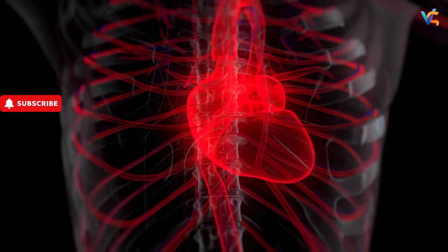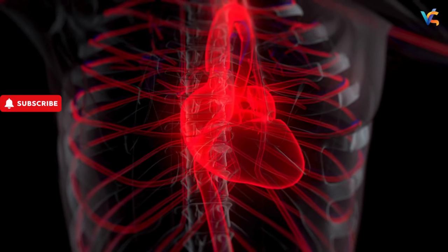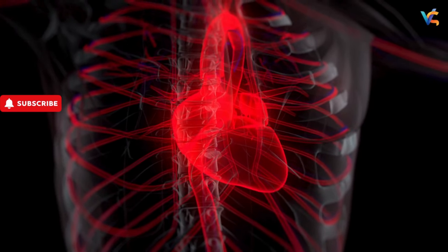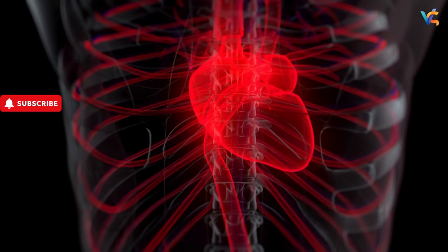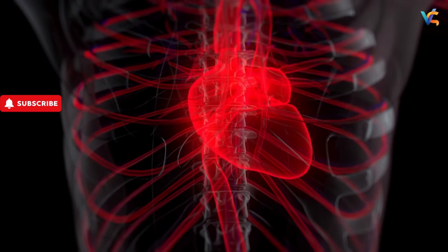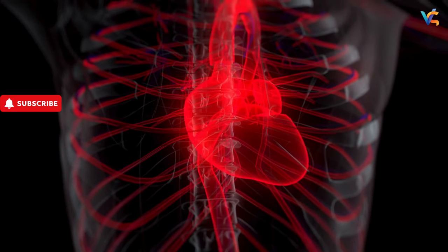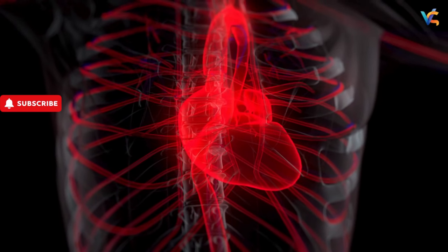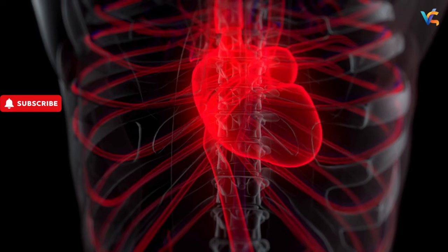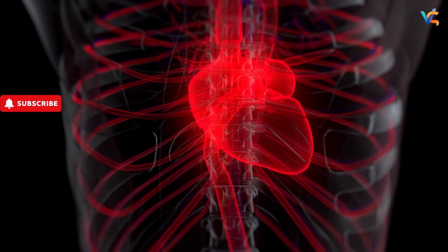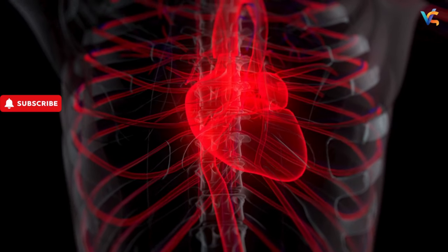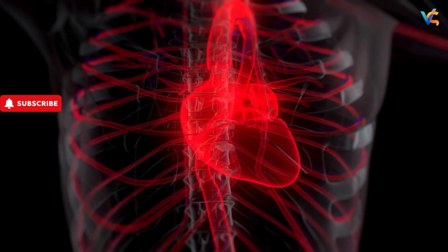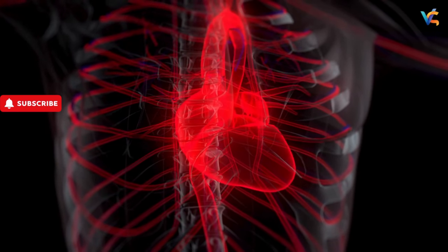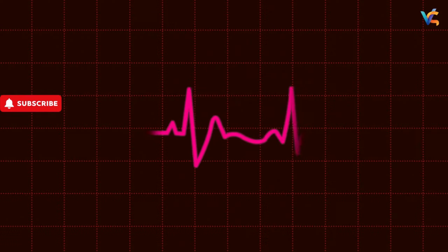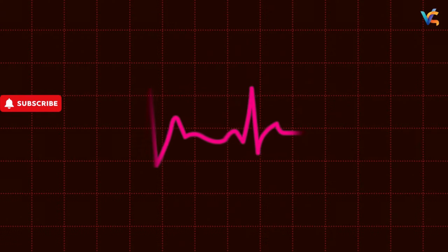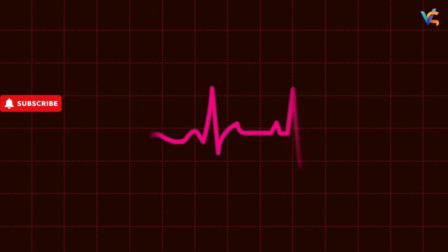Undersensing, for instance, can happen if the heart's own electrical signals are weak, or maybe coming from an abnormal place like a PVC, making it harder for the device to see them properly. Okay, so pacing helps with the slow rhythms. What about the dangerously fast ones? That's where the implantable cardioverter defibrillator, the ICD, comes in. Right. Its main job isn't really to prevent the fast rhythm from starting, but to be that crucial safety net that stops it once it does start, especially those life-threatening ventricular tachycardias or VT.